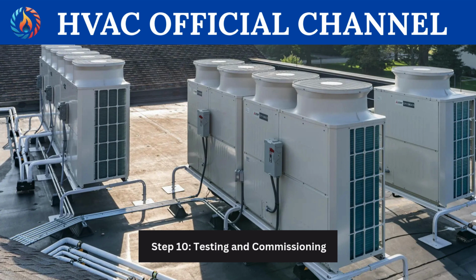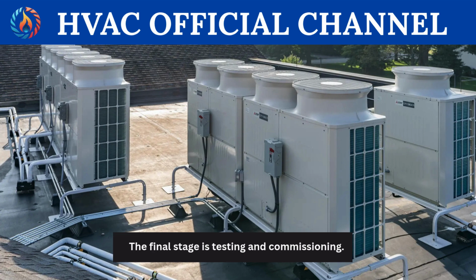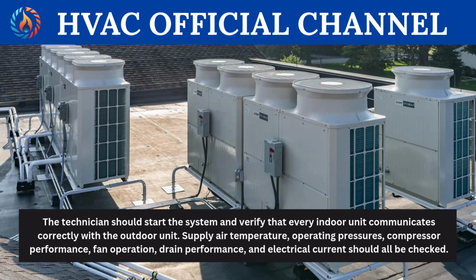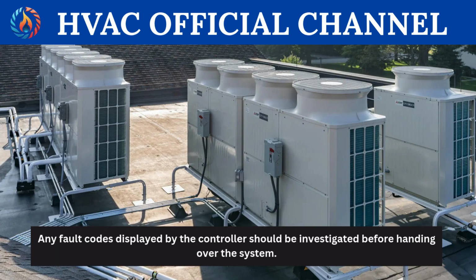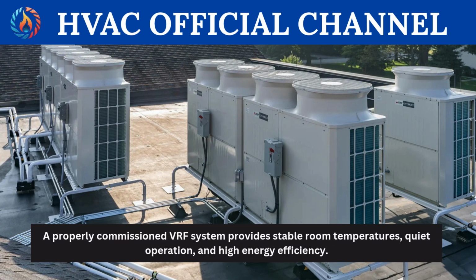Step 10. Testing and commissioning. The final stage is testing and commissioning. The technician should start the system and verify that every indoor unit communicates correctly with the outdoor unit. Supply air temperature, operating pressures, compressor performance, fan operation, drain performance, and electrical current should all be checked. Any fault codes displayed by the controller should be investigated before handing over the system. A properly commissioned VRF system provides stable room temperatures, quiet operation, and high energy efficiency.